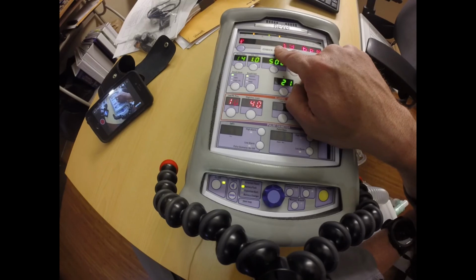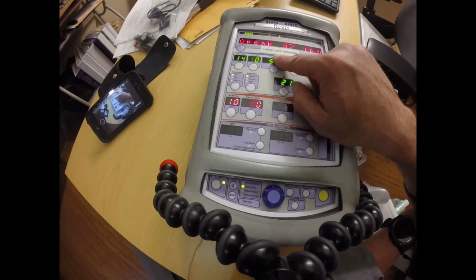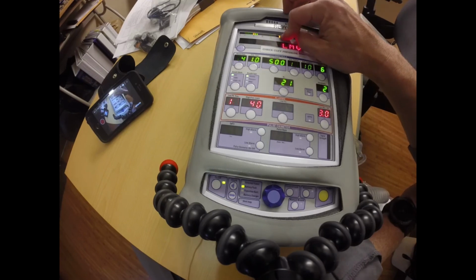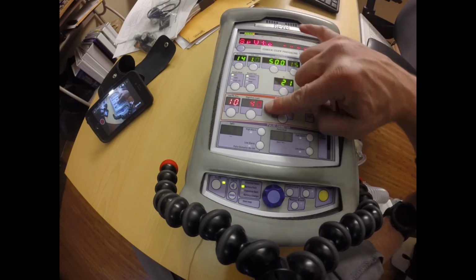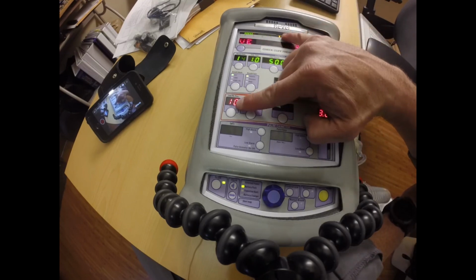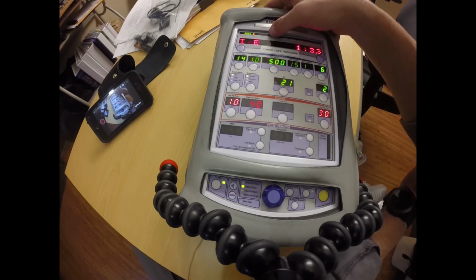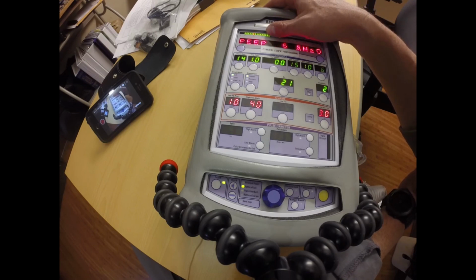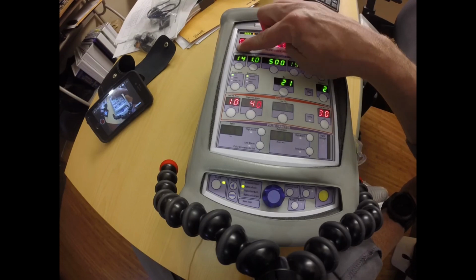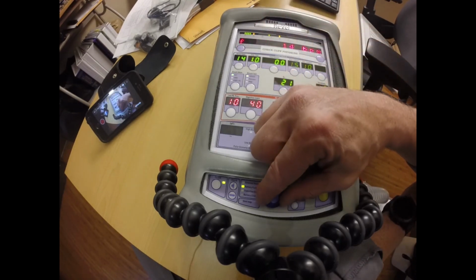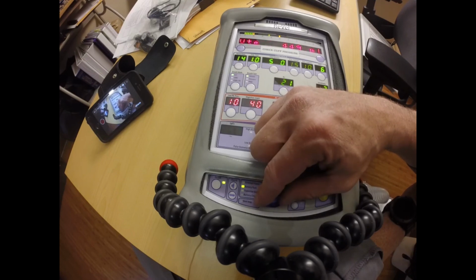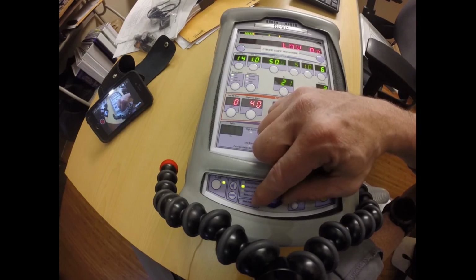Some other features that you will see: right now I have these orange lights illuminated up here, that tells me what my alarms are set at. So you'll see that my high pressure is at 40 and 40, and my low peak pressure is at 10 and 10. I can also trace that up, and it looks like my peak inspiratory pressure is right around 28 or 29. I can use the select button, so I can push that and toggle through my different parameters if I wish. So my expiratory tidal volume, minute ventilation, mean airway pressure, peak inspiratory pressure, and so on.